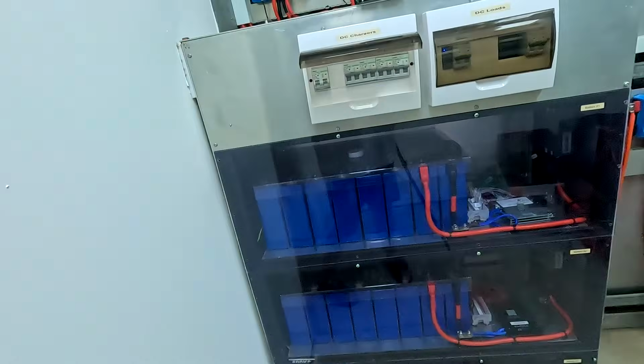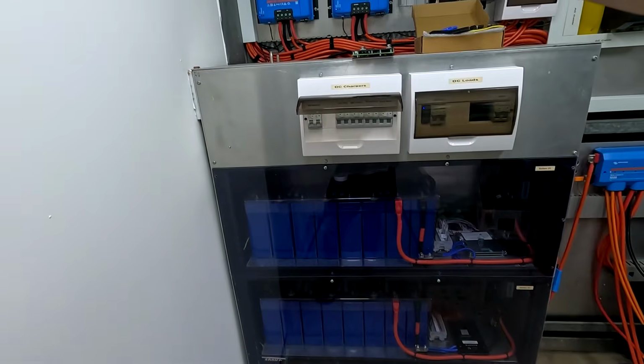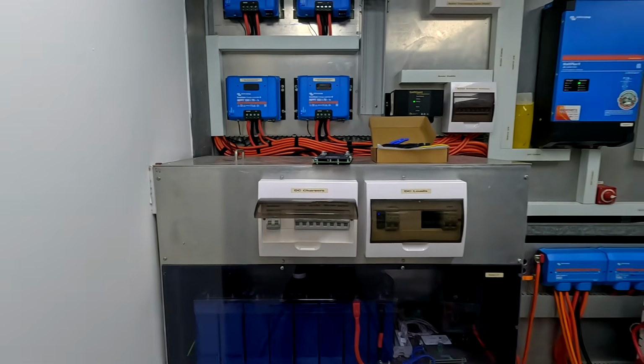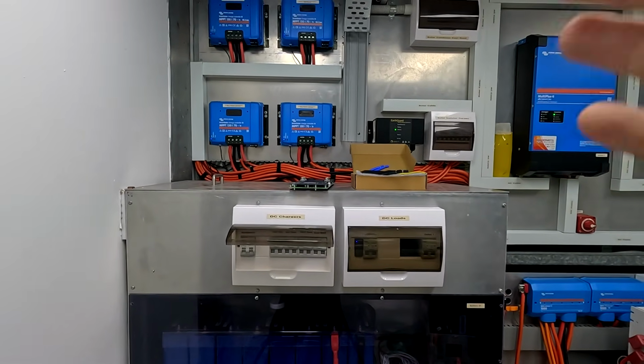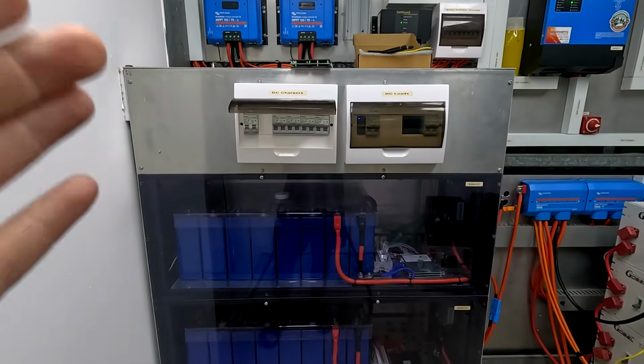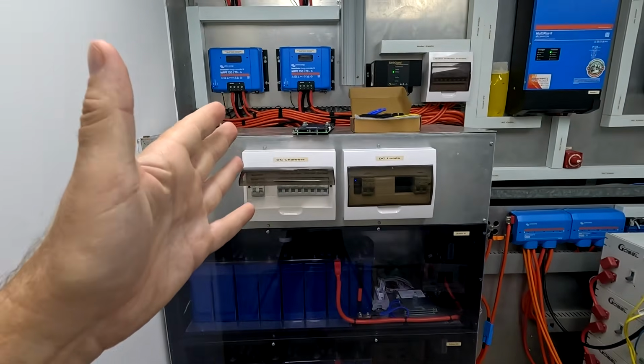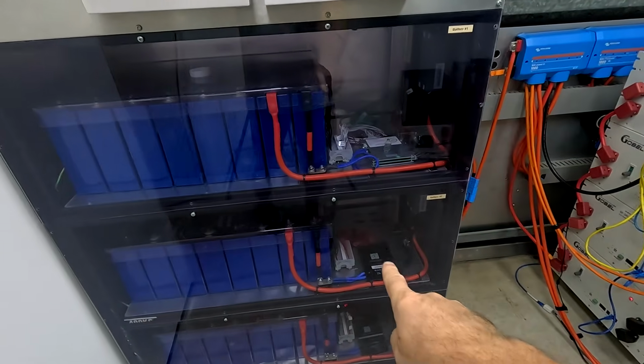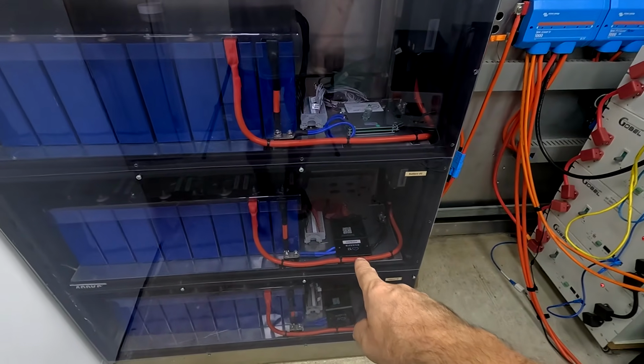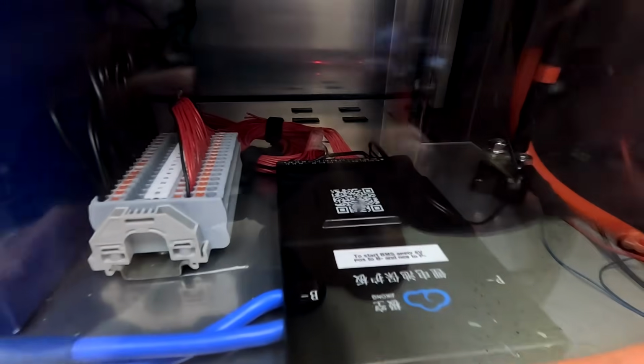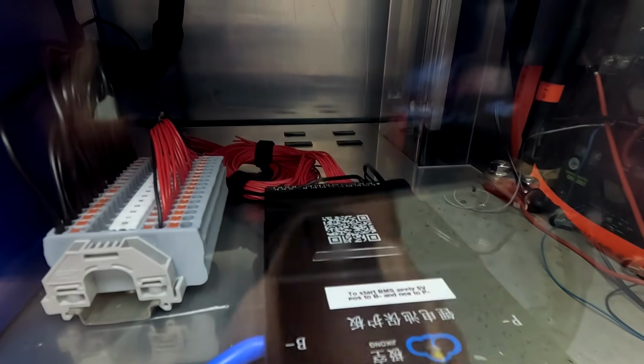communication? At the moment I don't have any communication here in my production system. I've got the battery shelf here, and all the charge settings are in the MPPTs and in the Multi-Plus, and they charge accordingly to 55.2 volts, then do an absorption phase, and then fall back to float voltage. And there's no communication between these batteries and these chargers. And this bit me back a couple of years ago already, when one of the batteries, I think it was the middle one here as well with the JK-Inverter BMS, they come with two temperature sensors. You can see them there and there.